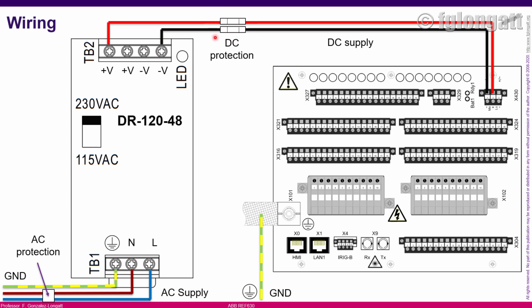In this case, we have a DC fuse to provide extra protection. The power supply has thermal overcurrent and short circuit protection, but I also include a fuse to provide redundancy. Here in the IED, we have a terminal required for grounding the metal case and providing reference.